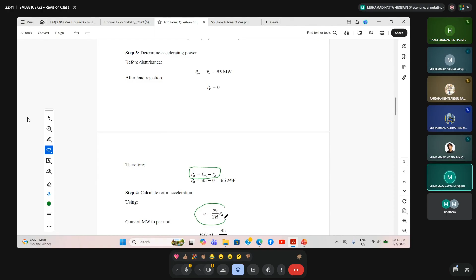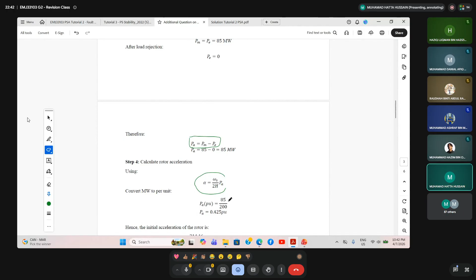Okay, so the power equal to mechanical power minus electrical power. 85 minus 0 equal to 85 megawatt. And after that, you have to determine the rotor acceleration by using this standard formula here. The alpha is equal to omega s divided by 2H times the accelerating power. And then you need to convert the megawatt to per unit. Okay, megawatt to per unit. So we have 85 megawatt divided by 200 megawatt.